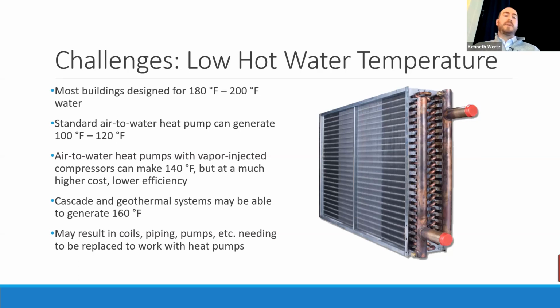They do have a newer technology of heat pump that can make warmer than 120. It can do 140 to 150, but you pay twice the cost for the unit and it's half as efficient. So it's not always a no-brainer that you would want to go with that technology. If you go with that cascade system or the geothermal, you can get even higher, like 160, 170. So you're pretty much back to where you were, and it makes it more likely you can just plug and play it into your existing hot water system. But that's not a guarantee.